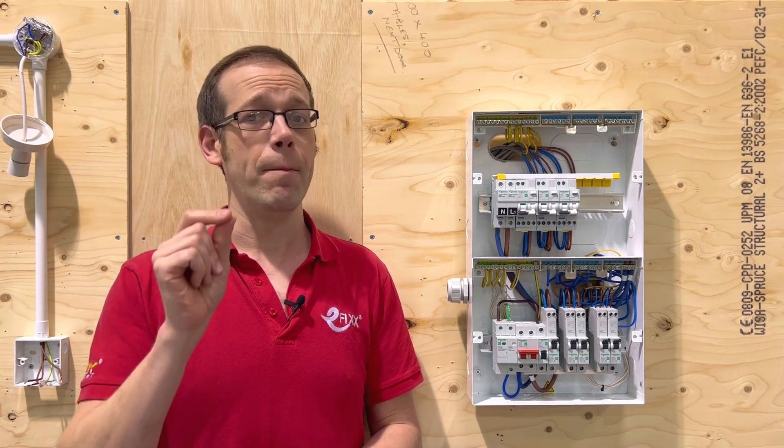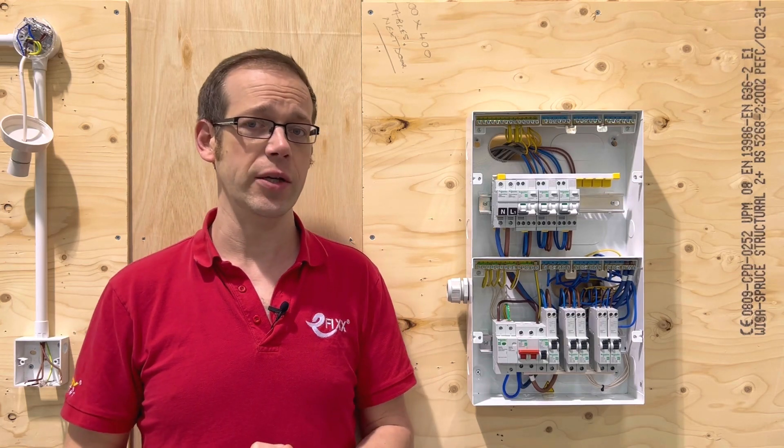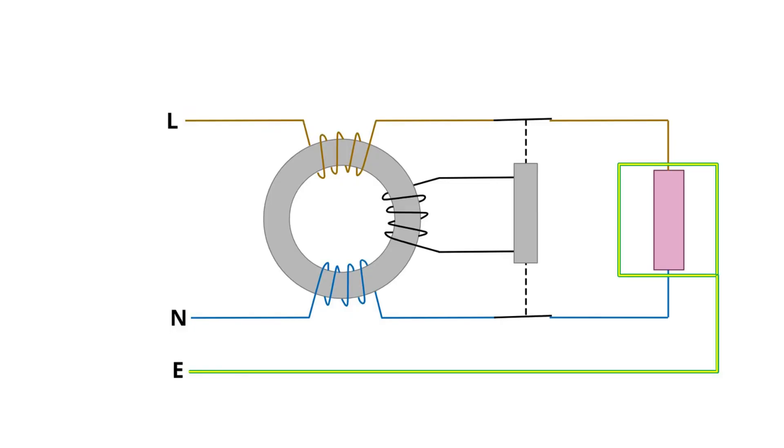But an RCD will offer a measure of protection in this situation. How? Well an RCD works by monitoring the amount of current flowing into the circuit down the line conductor and then back out of the circuit in the neutral conductor. If these two currents are the same the RCD knows that the circuit is healthy. If however it sees a difference between the current in the line and the current in the neutral it knows that somewhere current is flowing to places that it shouldn't either down the circuit protective conductor or through a person to earth and it will disconnect.